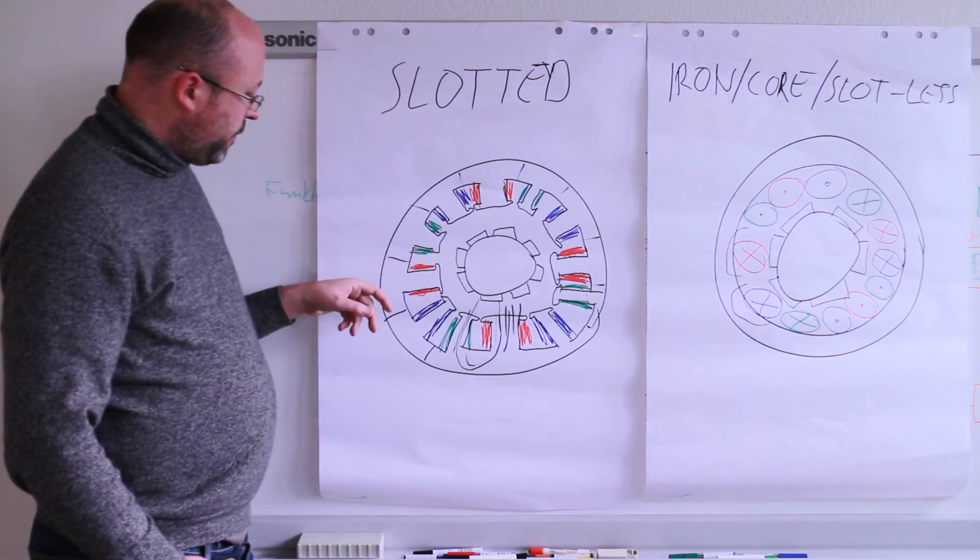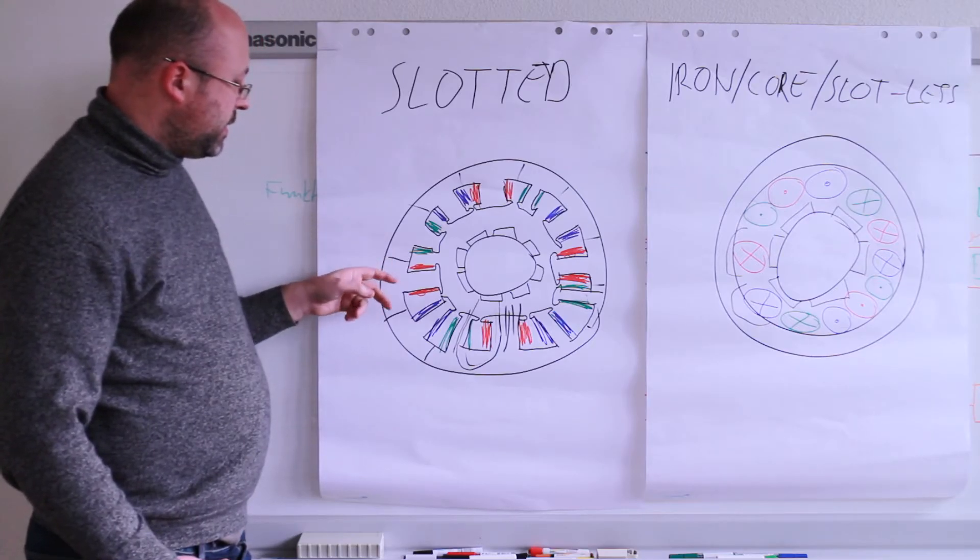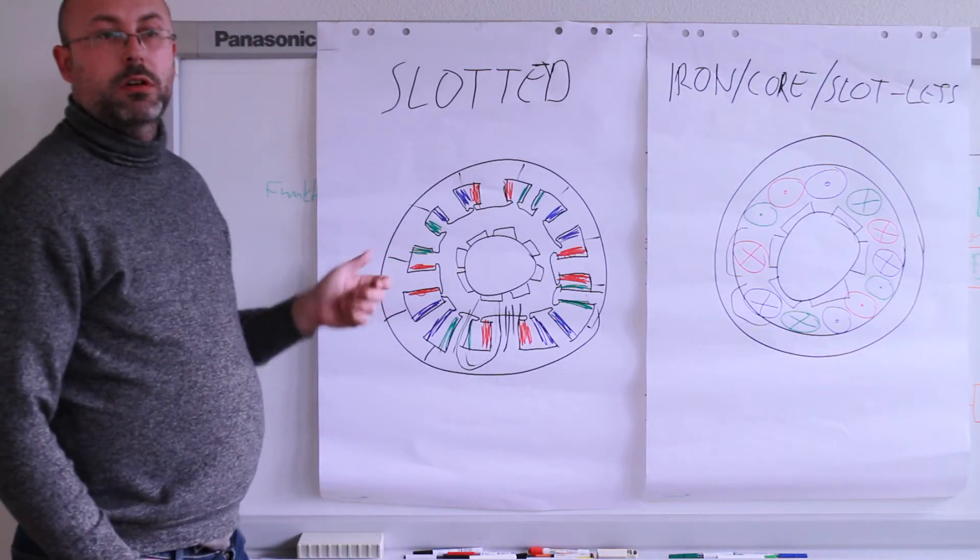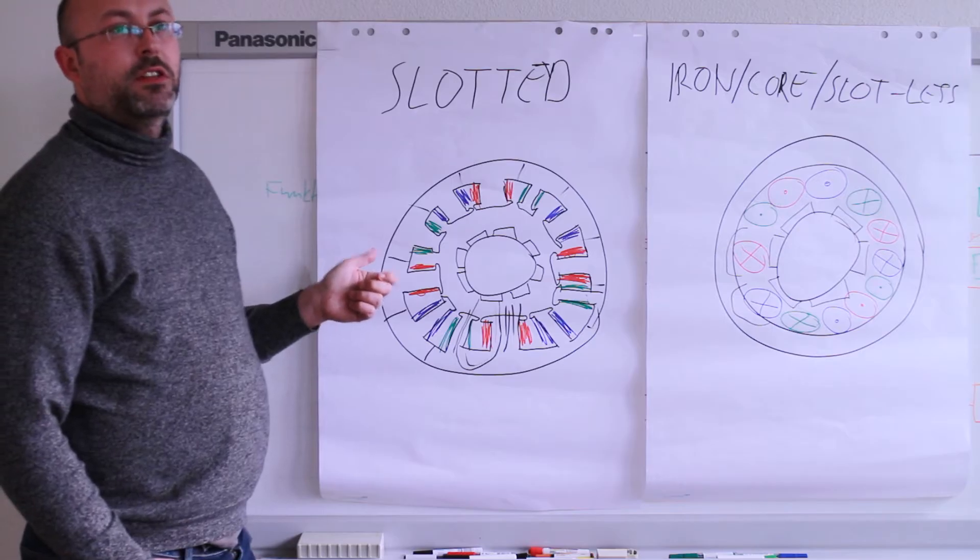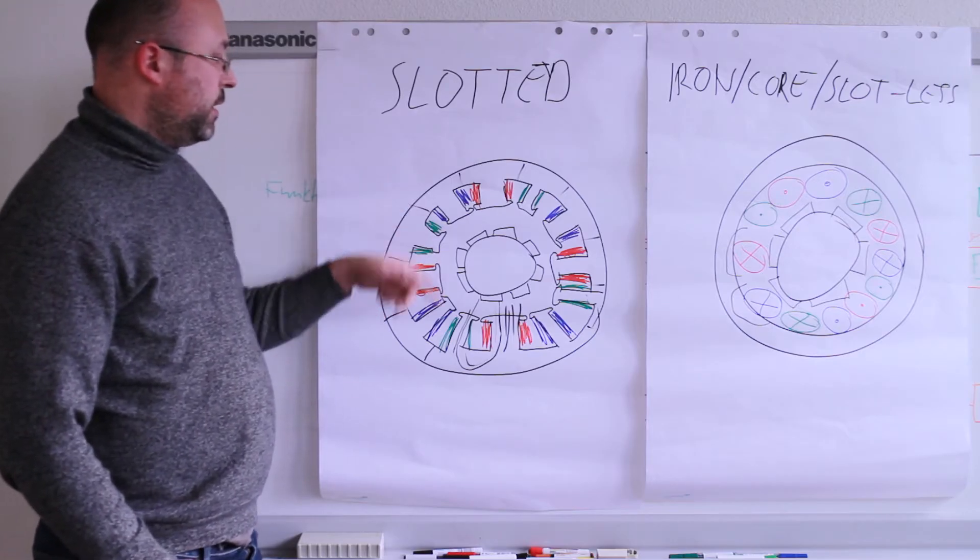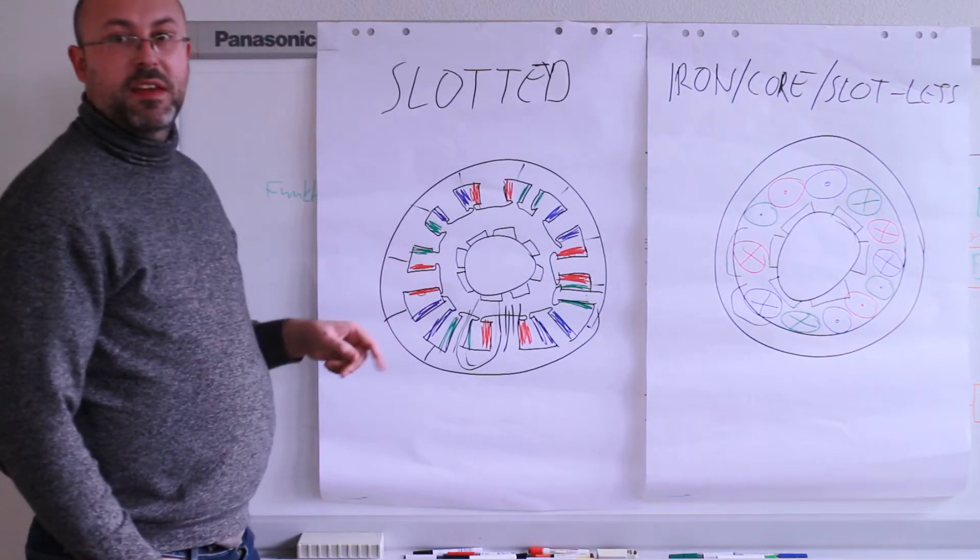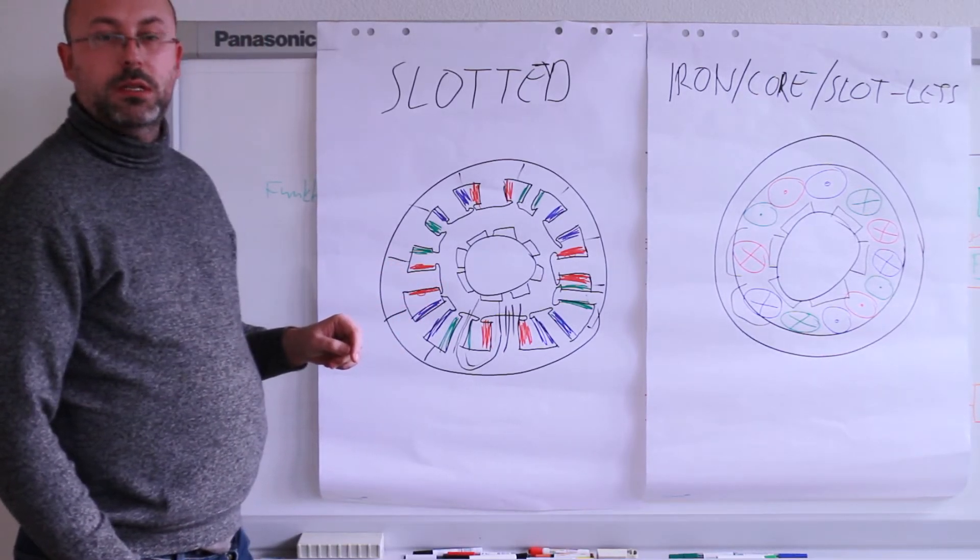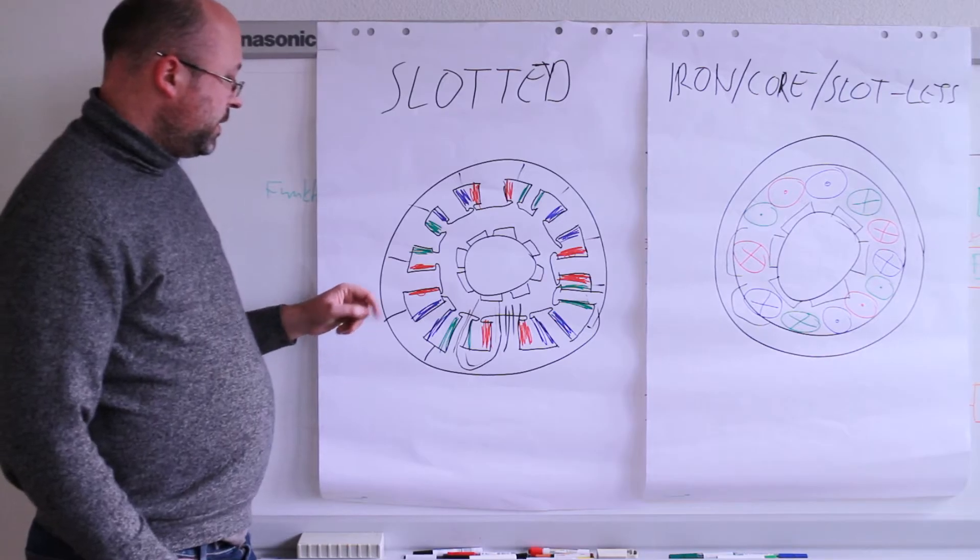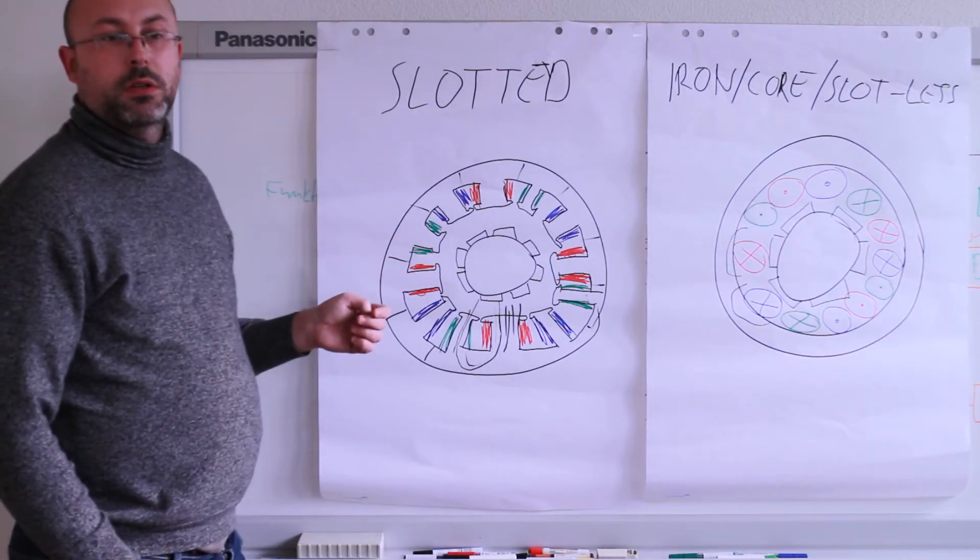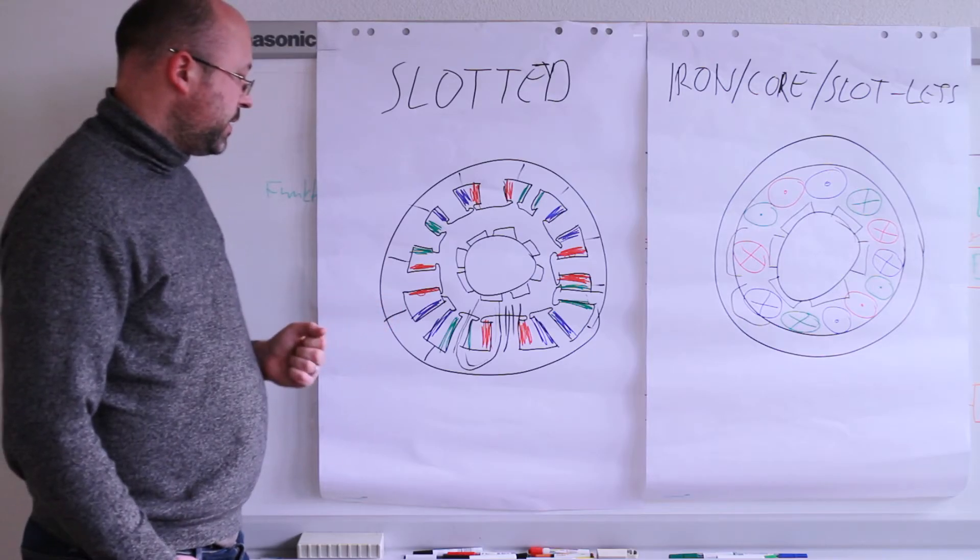If we go for a slotted segmented stator, we will have for a 60mm motor, if we have 0.5mm sheet thickness and 12 poles, we end up already having thousands of these small sheet parts. Very quickly we end up at the point where it makes sense to go for punching instead of laser cutting.